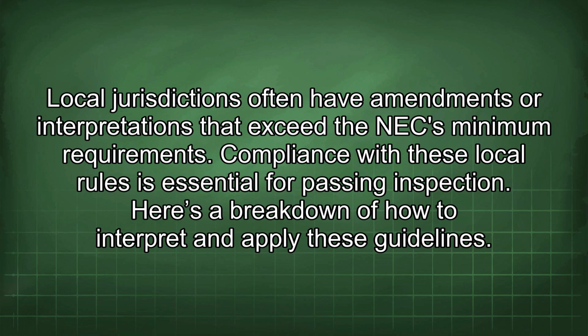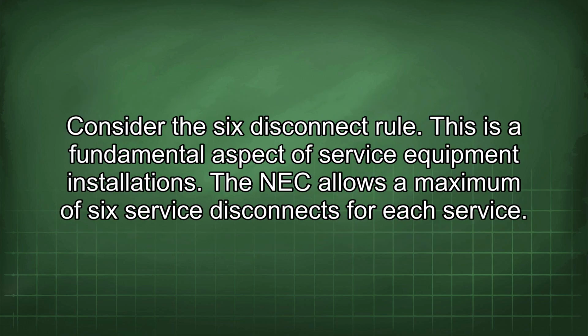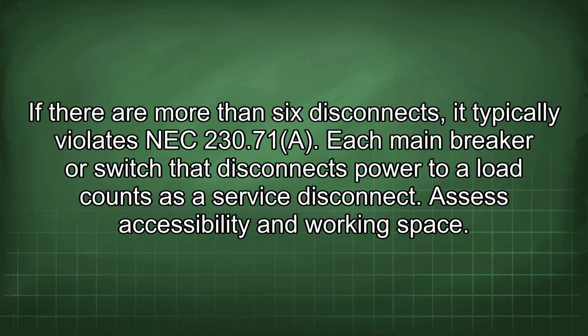Here's a breakdown of how to interpret and apply these guidelines. Consider the 6 disconnect rule. This is a fundamental aspect of service equipment installations. The NEC allows a maximum of 6 service disconnects for each service. If there are more than 6 disconnects, it typically violates NEC 230.71a. Each main breaker or switch that disconnects power to a load counts as a service disconnect.